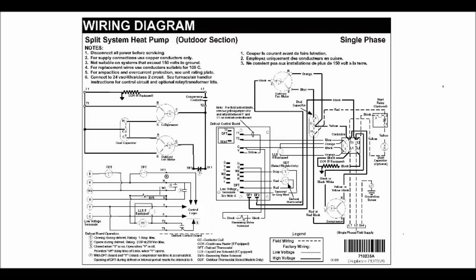The second part of a wiring diagram or schematic diagram that you need to understand is what's called the legend. And down here, this happens to have the wiring legend. And the field wiring, which is wiring that is done by the electrician or by the installers, is depicted by a dotted line. So over here, L1, L2, and ground in the dotted lines, you will not find inside the unit, but you will find connected to the unit. So that's the L1, L2, and ground right there.